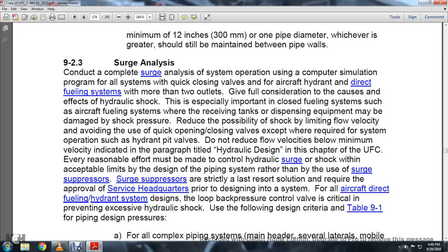Surge suppressors are strictly a last resort solution and require the approval of service headquarters prior to being designed into a system. For all aircraft direct fueling and hydrant system designs, the loop backpressure control valve is critical in preventing excessive hydraulic shock. Use the following design criteria with Table 9.1 for the piping design pressure.